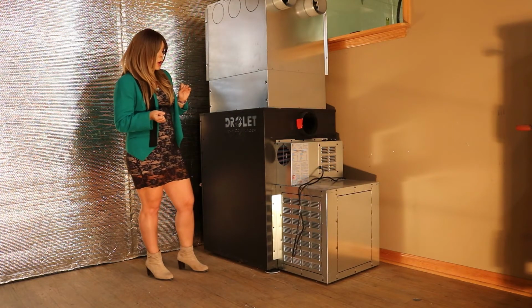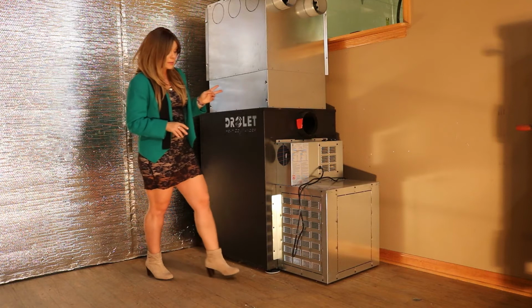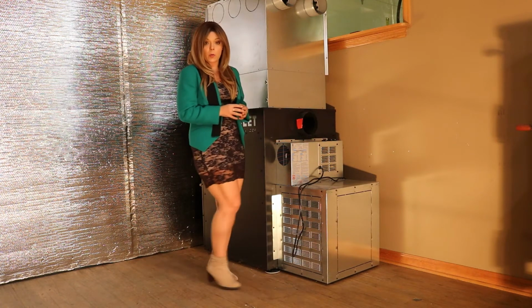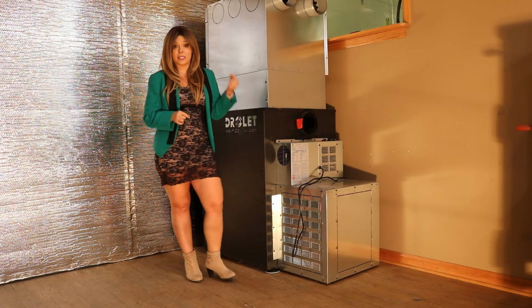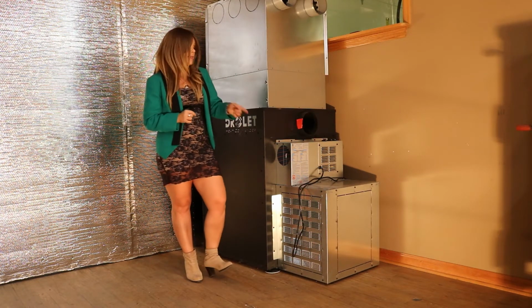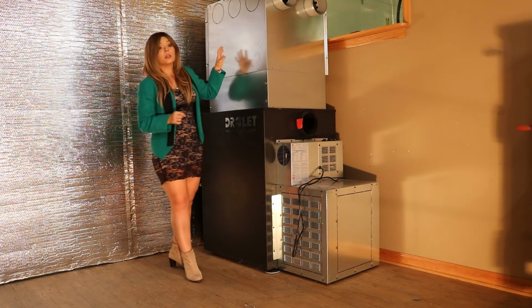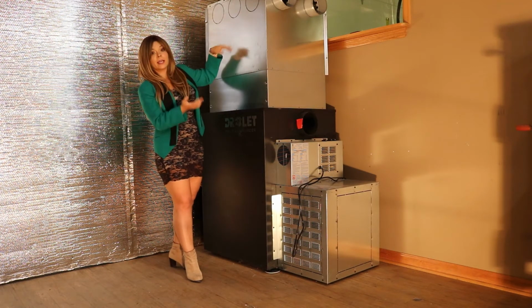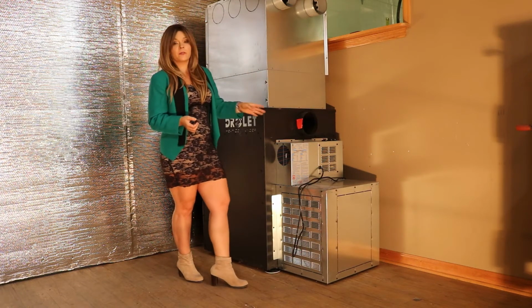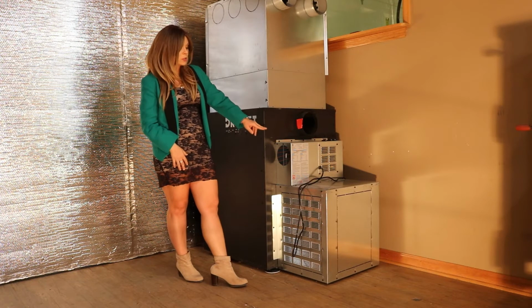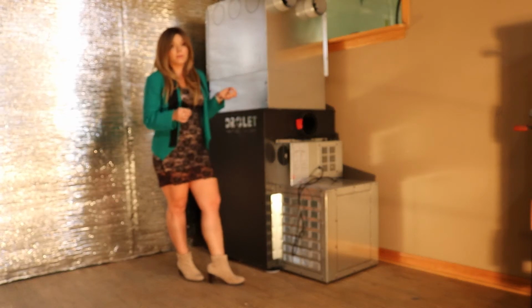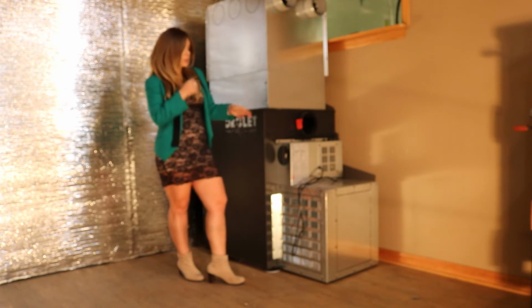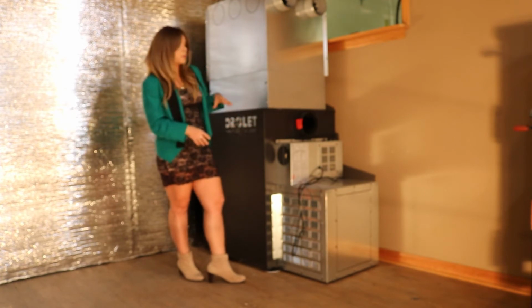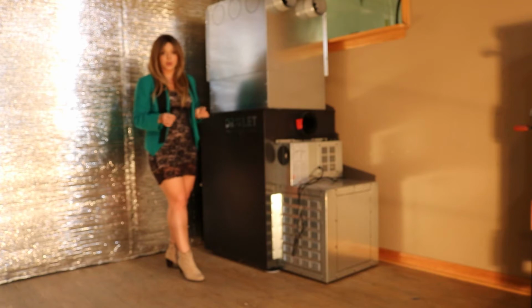Okay, so these blowers will kick on at different times. You also have to have this bottom blower hardwired into a thermostat. If it is not wired into a thermostat, then this blower will not register to kick on to call for heat and produce heat coming out the plenum, okay? So there are a couple different snap discs inside that we could troubleshoot. Generally, it's not a faulty item. If you've had a working system and suddenly the blower isn't kicking on and this isn't a brand new system, then it could potentially be a snap disc, but we're going to focus today on what else could possibly be causing this.